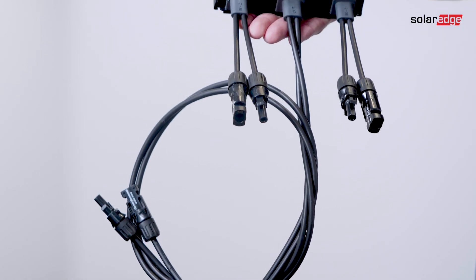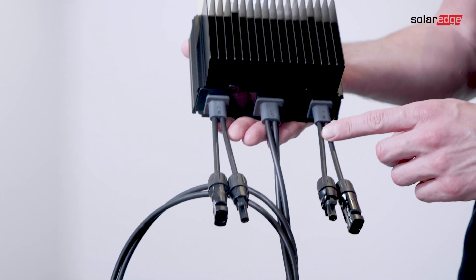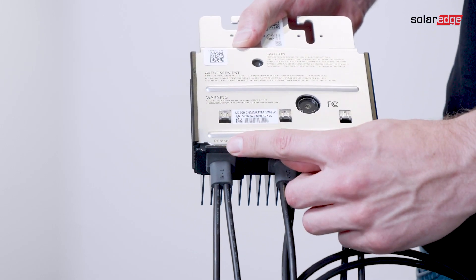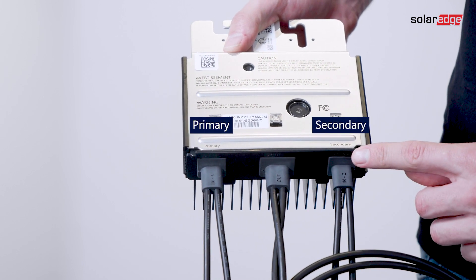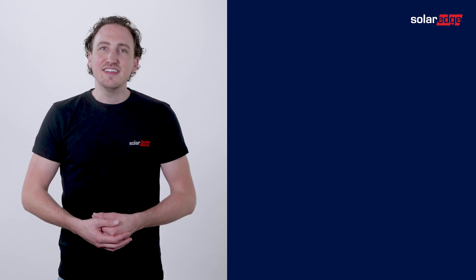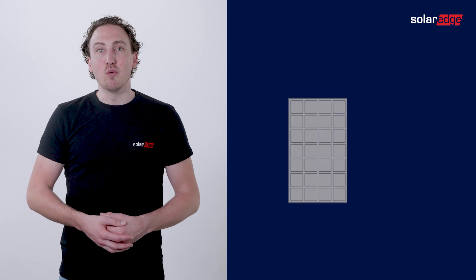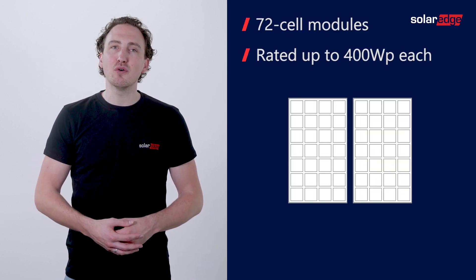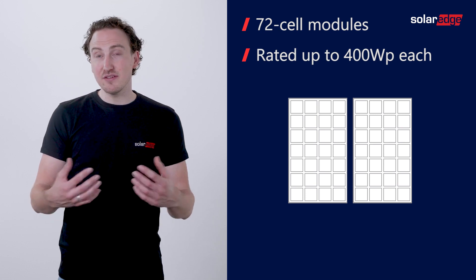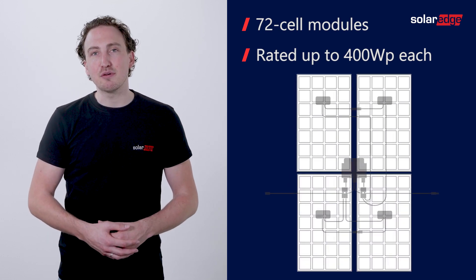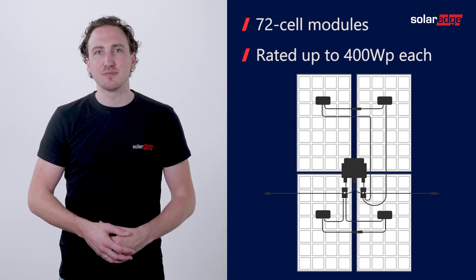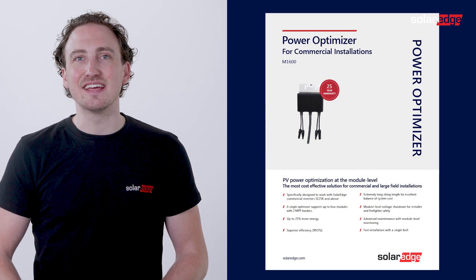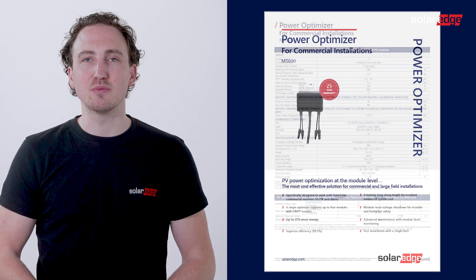The M1600 power optimizer has two separate inputs — one primary and one secondary input. This is clearly indicated on the optimizer backside. Each input supports the connection of one or two 72-cell modules rated up to 400 watt peak each, bringing us to a total of four PV modules per M1600 power optimizer. You'll find more detailed electrical specifications in the M1600 datasheet, available on the SolarEdge website.